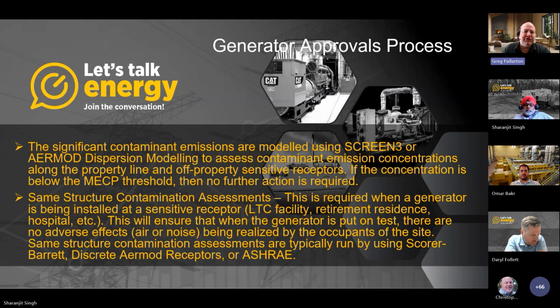Significant contaminant emissions—let's talk about global adjustment with a 5 megawatt generator. If you're looking to install that at your facility for peak shaving or GA, the significant contaminant emissions from that equipment must be modeled along with any other significant equipment at site, on a cumulative basis. You use Screen 3 or AERMOD dispersion modeling to assess those contaminant emission concentrations from the equipment along the property line and off the property line at sensitive receptors. If the concentration is below the MECP threshold, no further action is required—you meet the criteria with the ministry.